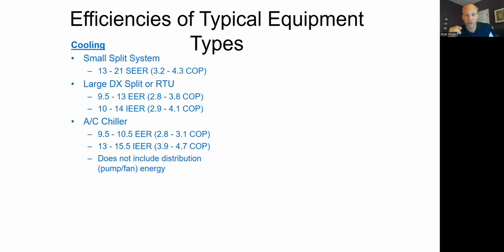From an efficiency standpoint, it's hard to compare these to other things. And by the way, it's always hard to compare different types of products, like I mentioned on module 1. Trying to compare a heat pump to a furnace, to a boiler, to a VRF, to a rooftop, to a chiller, it's hard because they're all doing it a different way. Specifically, one of the big challenges is if you have, this says air-cooled chiller, but water-cooled chillers are the same way. If you look at the efficiencies for air-cooled chillers, they do not include the energy that is required for the fans of the air handlers or for the pumps on the water side.